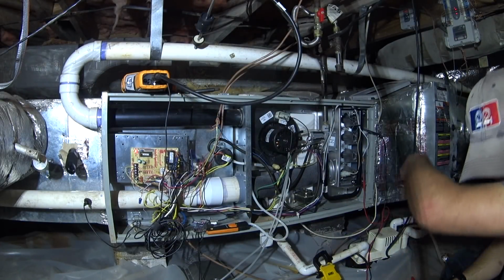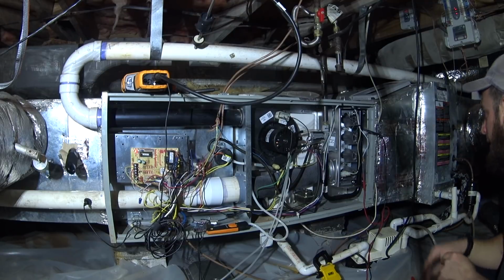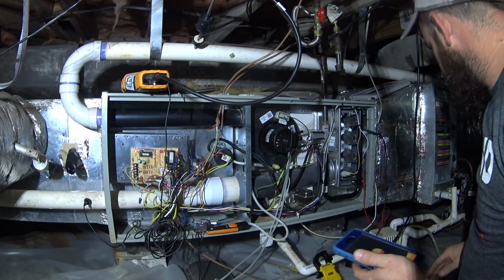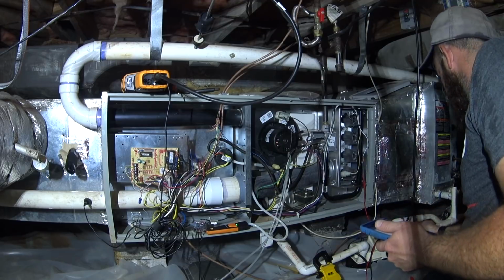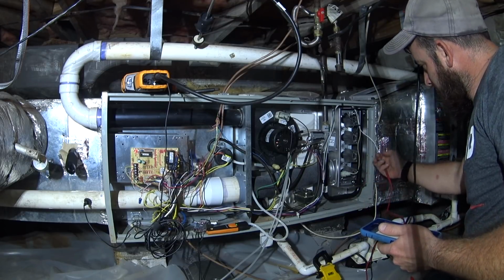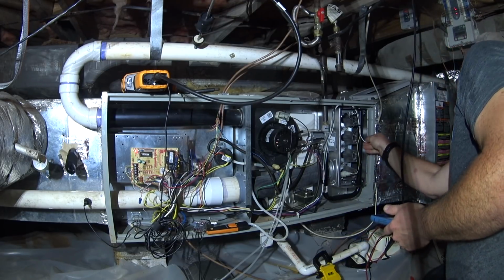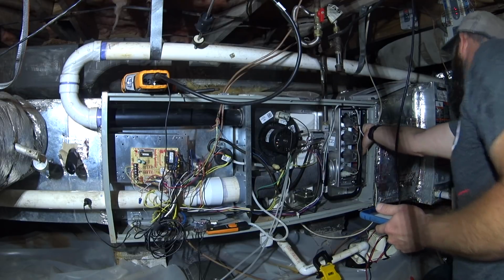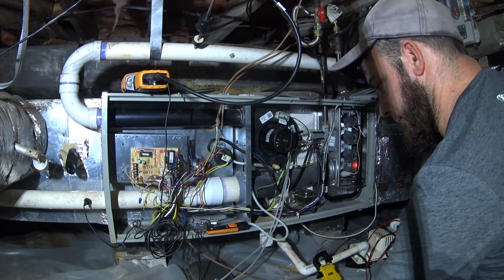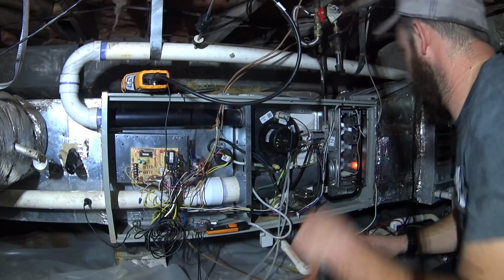Flame signal is 2.4. Pull the flame sensor out, plug it back in, while we put the burner door back on.